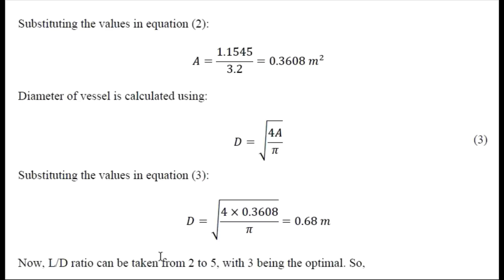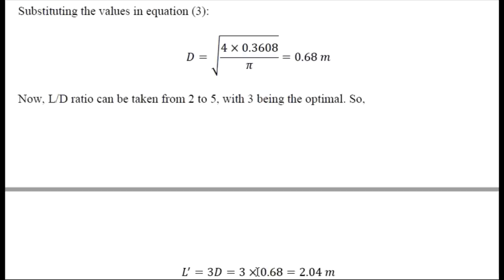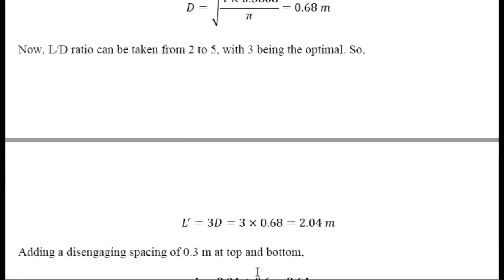Now to calculate the height or length of the separator, we know that L by D ratio is 2 to 5 with 3 being optimal. So we will be using 3 as L by D ratio. Using this we can find the height of the separator as 2.04 meter.